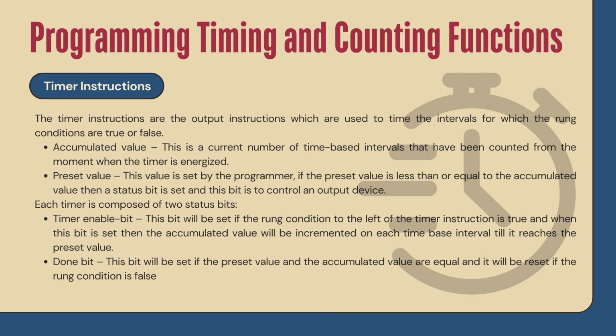When the accumulated value is greater than or equal to the preset value, the status bit is set to control an output device. Next is the timer enable bit, which is set when the rung condition to the left of the timer instruction is true. When this bit is set, the accumulated value increments on each time base interval until it reaches the preset value. Lastly, the done bit is set when the accumulated value equals the preset value, and it is reset when the rung condition becomes false.